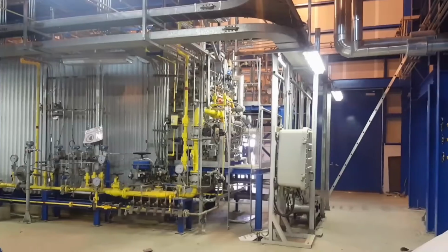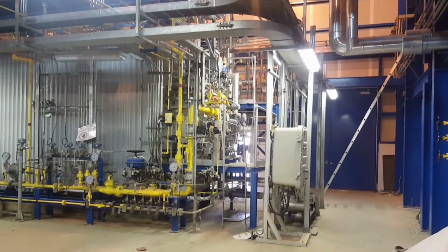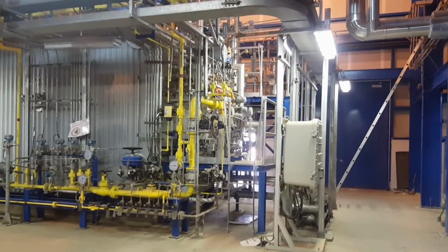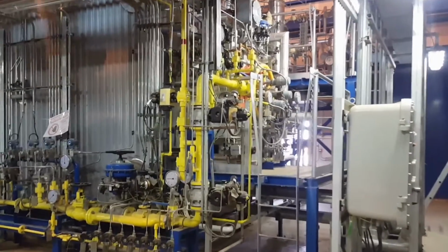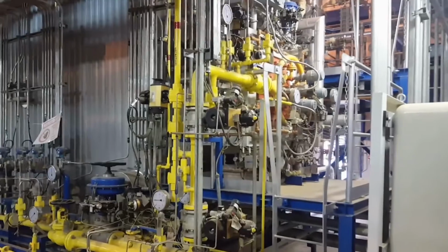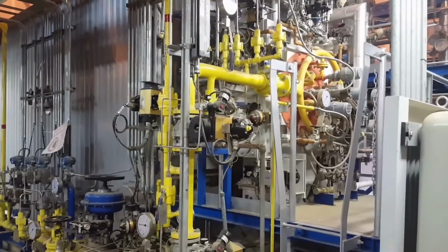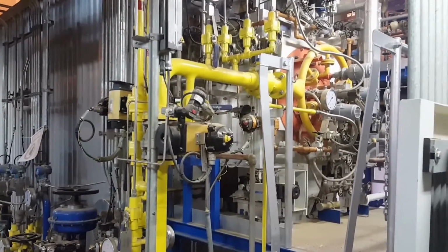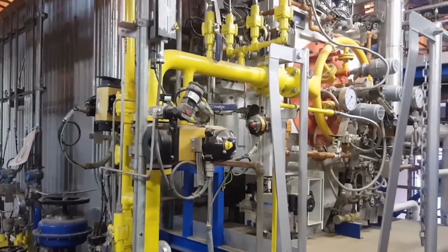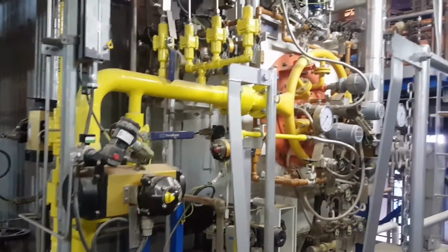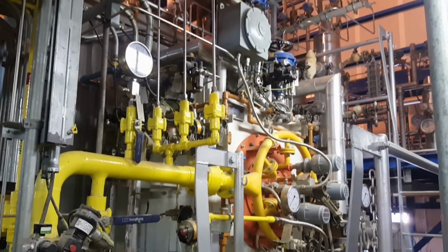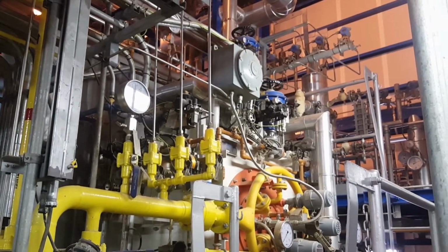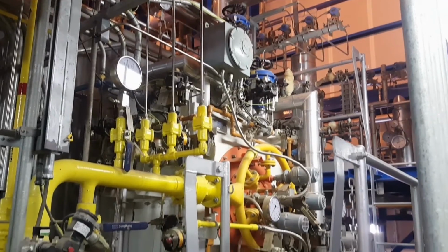The main function of all burners is the same, to inject a mixture of fuel and air into the boiler's combustion area. Burners are used with fuels that mix easily with air, such as natural gas, oil, or pulverized coal. This burner, for example, is a typical gas burner. It uses dampers or registers to regulate the amount of air entering the burner. Pipes called spuds inject natural gas into the boiler.